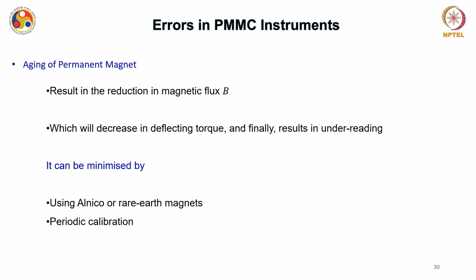We have seen that the deflection torque is proportional to the current, but it is also proportional to the magnetic flux in the air region. So if there is a decrement in the magnetic flux, there will definitely be a decrease in the deflection torque, and again the result will be under reading. It can be minimized by using alnico or advanced magnetic materials based on rare earth materials, like neodymium iron boron compound NdFeB in different compositions, and also by periodic calibration of the tool, so regular calibration can help improve these errors.